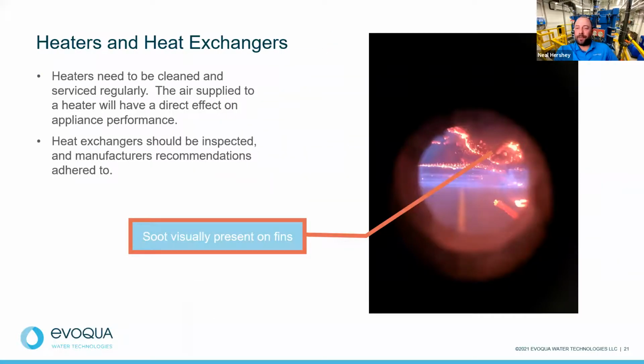One of the things is a visual inspection. On a direct fired heater, you're going to start to see a buildup of soot potentially in the heat exchanger fins. Most heaters have a little viewing port you can look in. If you see a bunch of stuff glowing in there, it probably needs to be cleaned. That's something that should be done preventatively.